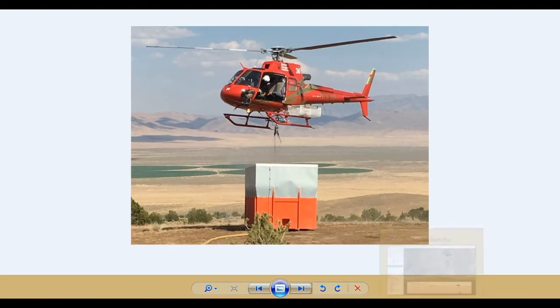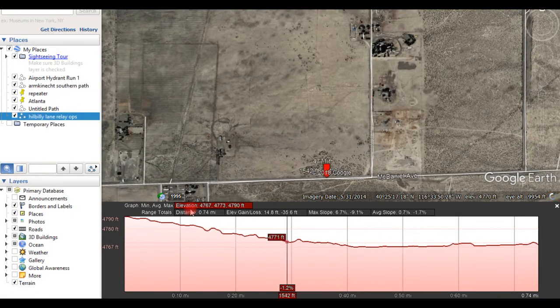And for the structure counterpart, you guys can use 2.5 inch, especially in the volunteers and the rurals. A 2.5 inch hose, you could do it. You would just have to put an engine or a couple of engines in between here. Usually every 1,200 feet, that's the average.